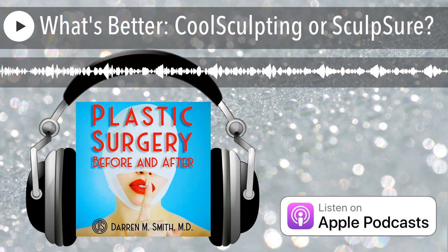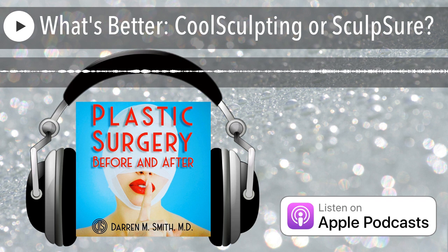So I'd like to go ahead and divide these minimally invasive fat removal procedures into two categories based on how they are achieving fat removal. The first category is cryolipolysis, and cryolipolysis is the process by which fat cells are destroyed by exposing them to extreme cold temperatures. And the only device that fits into this category of the three that we're discussing here is CoolSculpting. The other two devices, the SculpSure and the TrueSculpt ID, fall into the category of devices that cause fat cell destruction through heat. So essentially by either using cold in the case of CoolSculpting or heat in the case of SculpSure and TrueSculpt, we are bringing fat cells to the point that they actually trigger cellular self-destruction in a process called apoptosis. So different means of arguably achieving the same result.